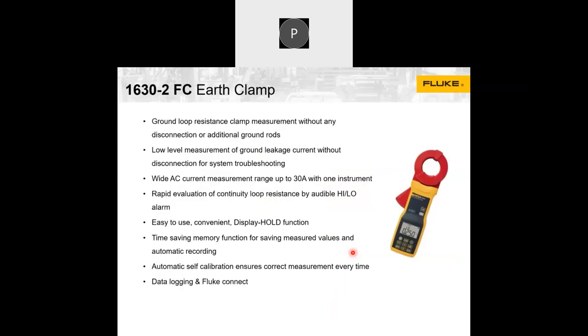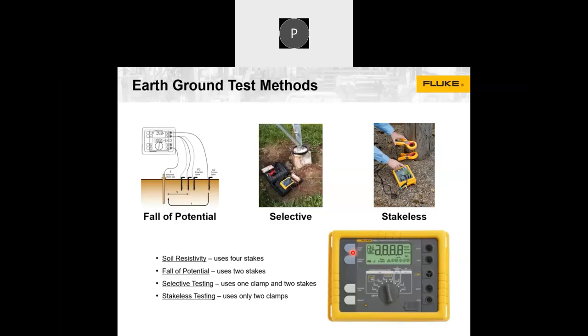These 4 methods are important because you'll have different facilities, and you may not be able to apply the same method everywhere. In a building, you may not be able to use stakes - there you'd use the clamp. In the field, you can use stakes. But if the substation is completely concreted, you may not be able to use stakes, and that's when you'd have to use these kinds of clamps.